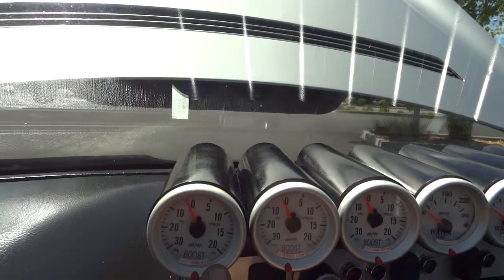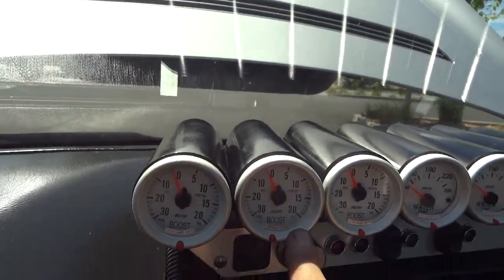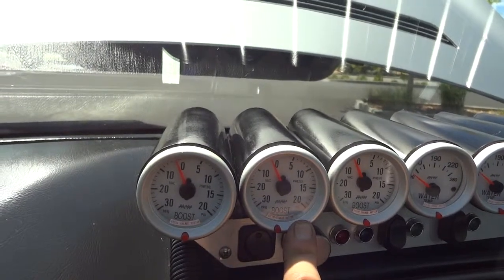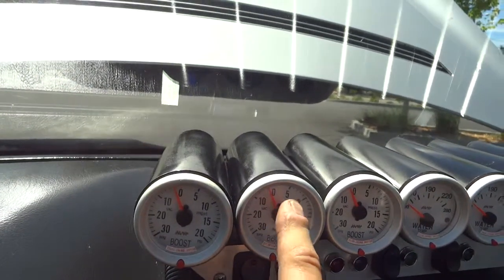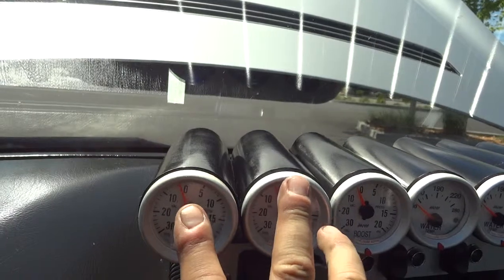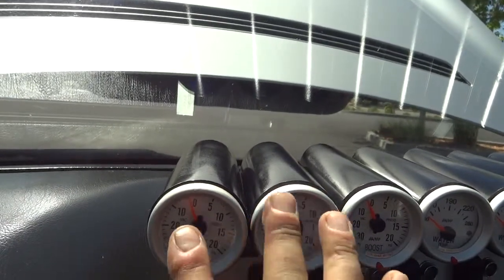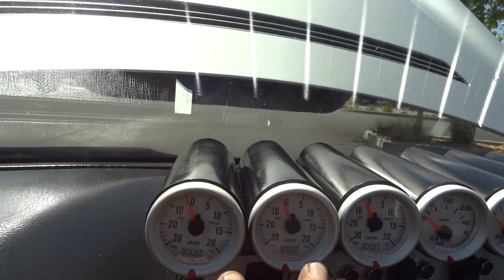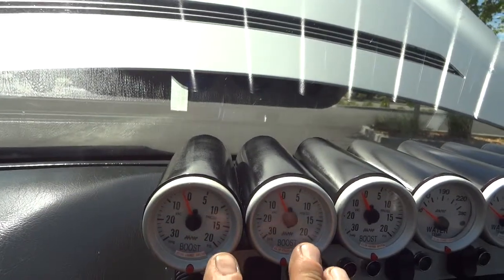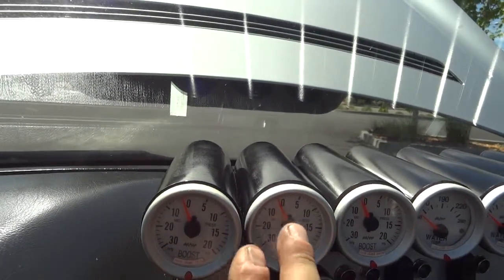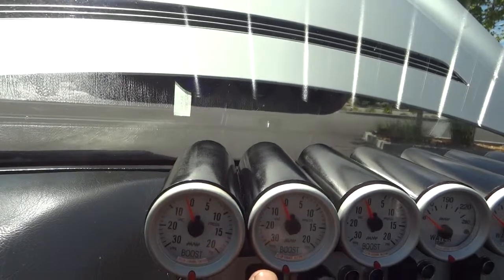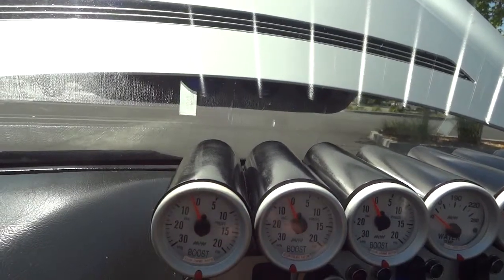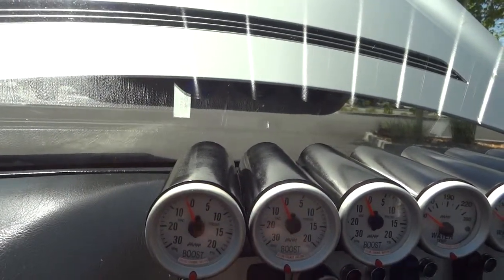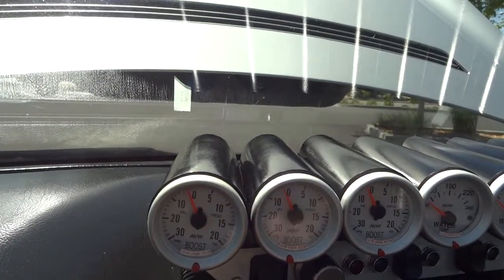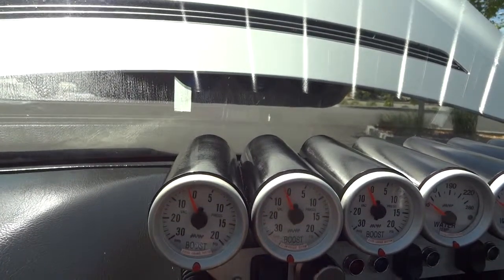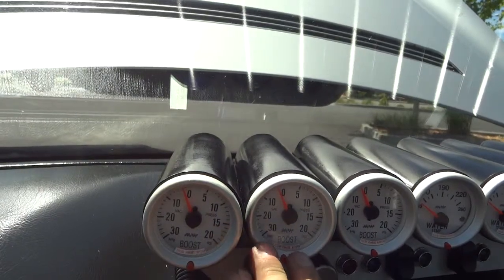This gauge measures the pressure before that, and this gauge measures the pressure after the filter housing. So when there is a difference between the 2 needles, that's when you can see the filter is getting clogged up. When everything is clean, there is only about a 1 psi difference between the 2 gauges. There is always some pressure drop as the fuel goes through the filter, because the filter creates some resistance.